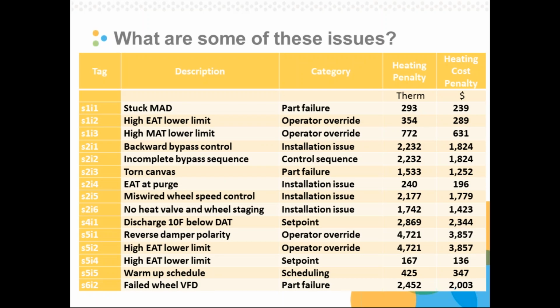What do those issues look like? So here are a bunch of issues. This is not a complete list, but just a variety of the things that we encountered. Stuck mixed air damper. We had a lot of operator overrides with respect to exhaust air temperature limits, mixed air temperature lower limits. We had some dampers wired backwards, some incomplete sequences, torn vibration damper, all sorts of things. Exhaust air temperature sensor located right at the purge, miswired wheel and speed control, conservative discharge air temperature set point, failed VFD. These issues range in penalty and cost from a few hundred therms or dollars to a few thousand therms or dollars per year.